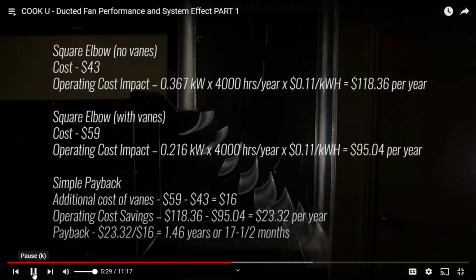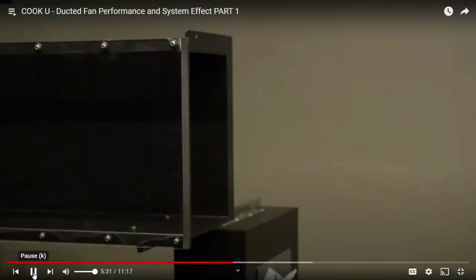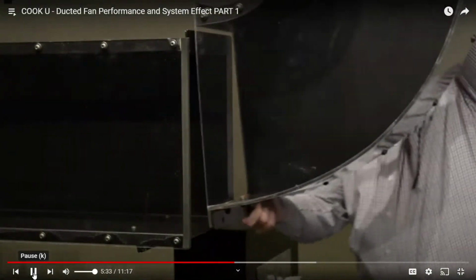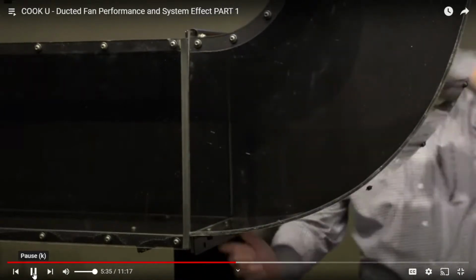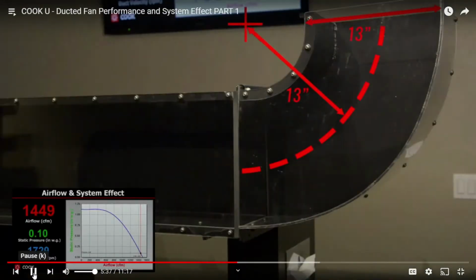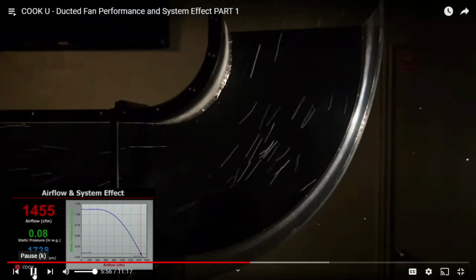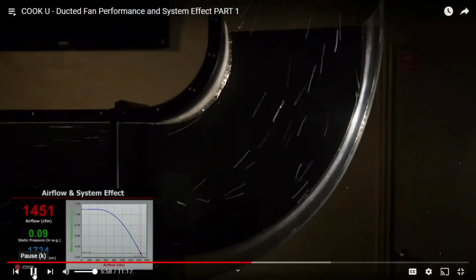The next fitting we will evaluate is called a short radius elbow. A short radius elbow has a centerline radius approximately equal to the duct dimension in the same plane. Our duct is 9 inches by 13 inches, so the centerline radius of this elbow is also 13 inches. As you can see, the pressure drop is very low, with an airflow just 30 CFM short of our baseline setup. We see very little turbulence in the fitting, reinforcing the result.